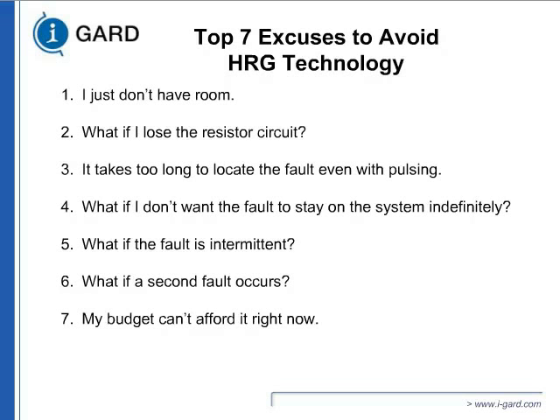And what if the fault is intermittent? People who are listening say, hey, you say that an intermittent fault is a dangerous one. How does high resistance grounding prevent me from that? And what if a second fault happens? When a second fault happens, if the first fault is not cleared, you will have a phase-to-phase fault. The system will trip. And the last thing was, my budget can't afford it right now. I just don't have money to spend on these things. So let's see if we can answer one by one.